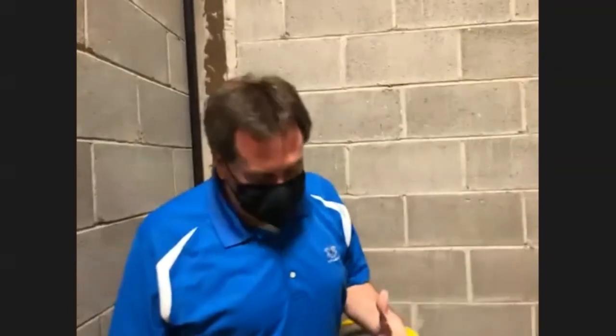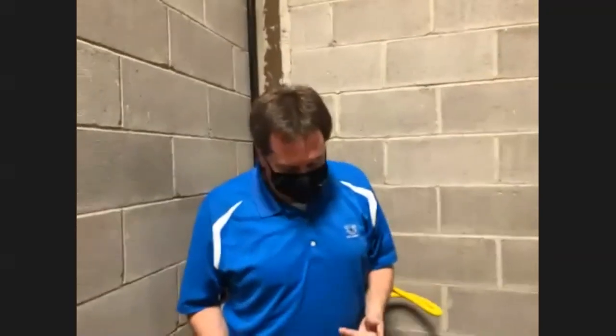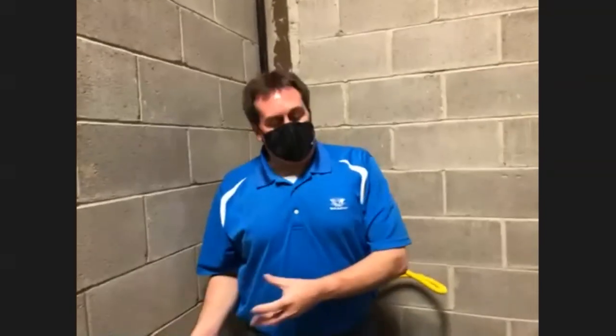It's easier on the pump. The pump does not have to work as hard trying to recirculate everything, and it allows things to go back into your main tank. You must have a filter on your tank. So when it's going back through, it's actually refiltering itself when it comes back to the burner again. So again, it allows the pressure on the pump to operate a little bit better, and you're refiltering that fuel.